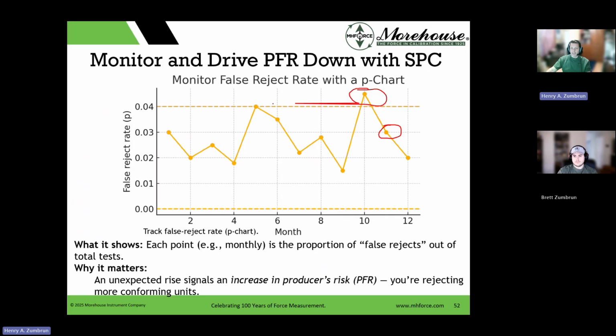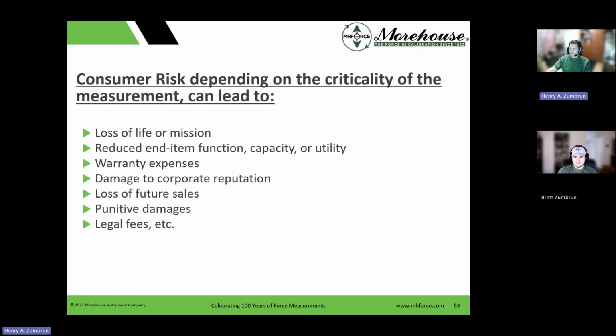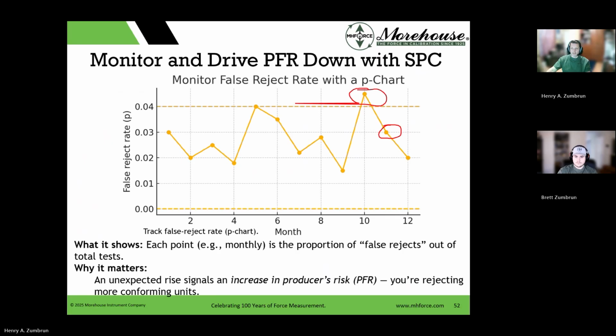I don't know that many people that are doing this, so your best step is probably just to use your calibration provider with the lowest uncertainties. But if you do this, it can show a lot of trend analysis, and detection is always a good thing. So monitor how often the lab falsely rejects in-tolerance items. I just had this: when people send a load cell that's 10,000 pounds, they say it's 10,000 pounds high range and they get a low range calibrated. We did that full analysis and determined that the low range, percentage-wise, is always going to be higher as a percent of full scale than the higher range.